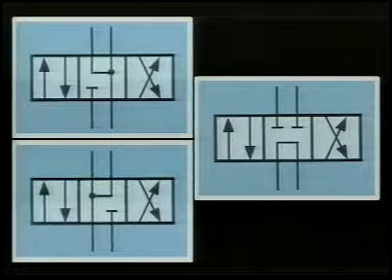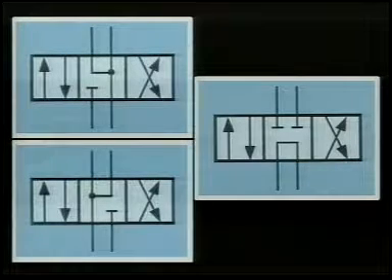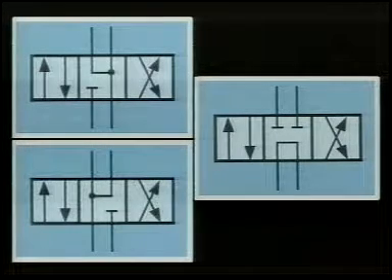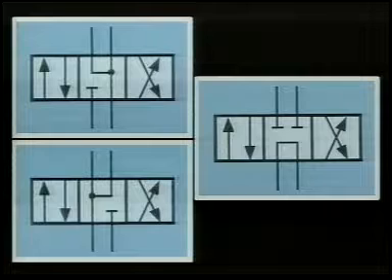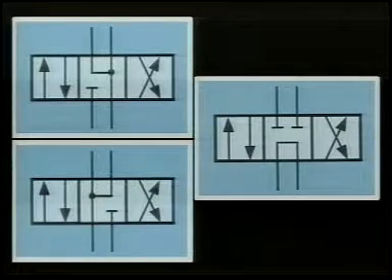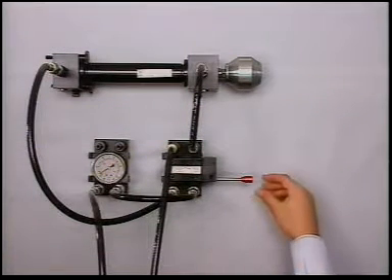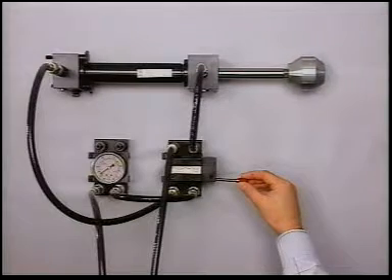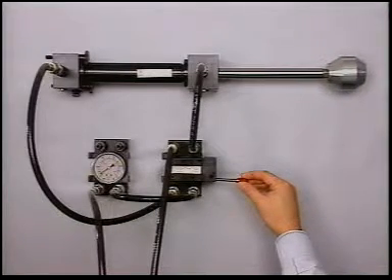In the valve represented by this circuit symbol, the function has the same effect on the drive units. It stops them. But the pressure port to the pump and the reservoir return line are connected. This means that when the 4-3-way valve is in the mid position, the pump doesn't have to build up any system pressure.